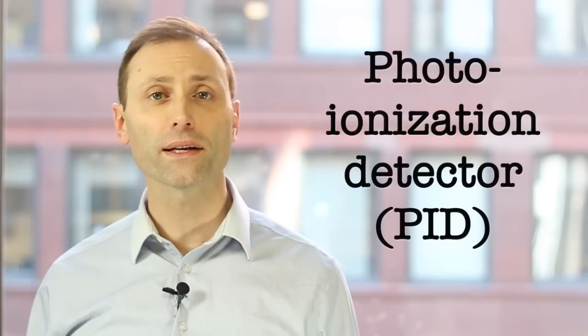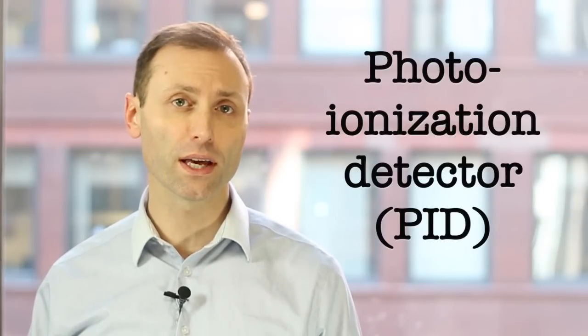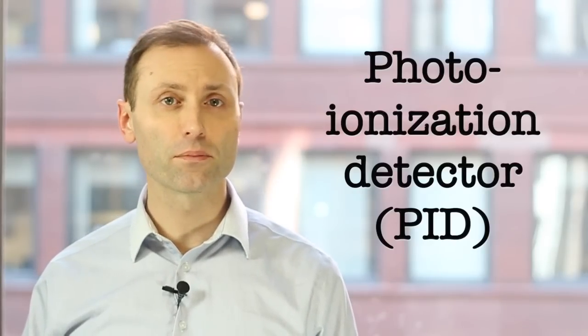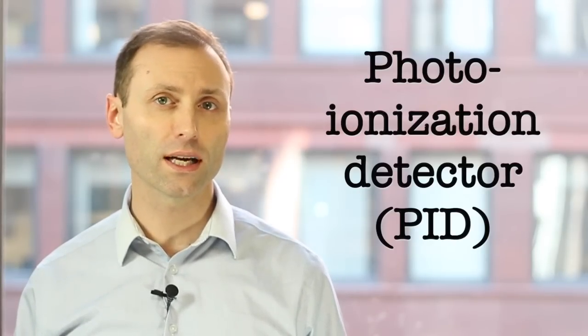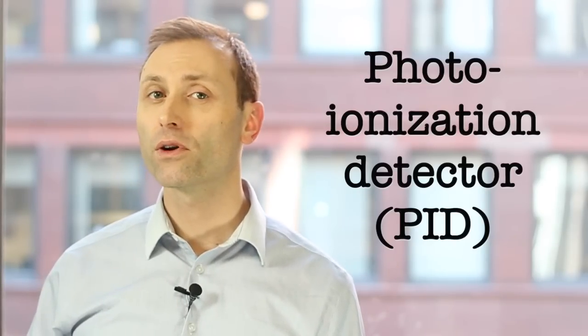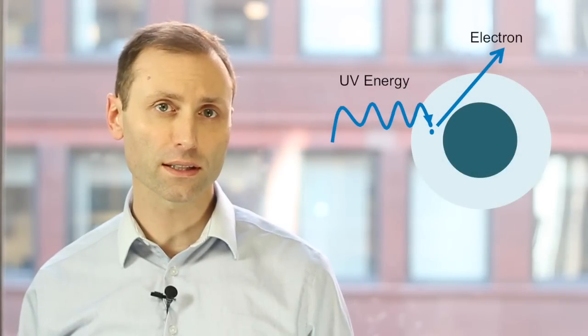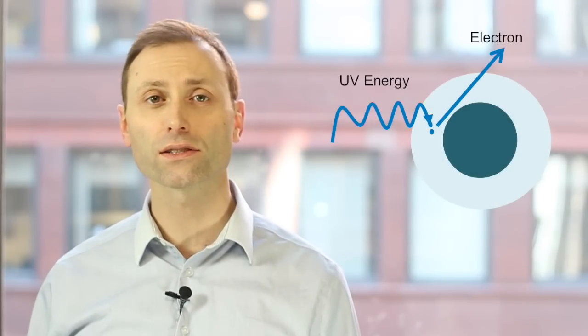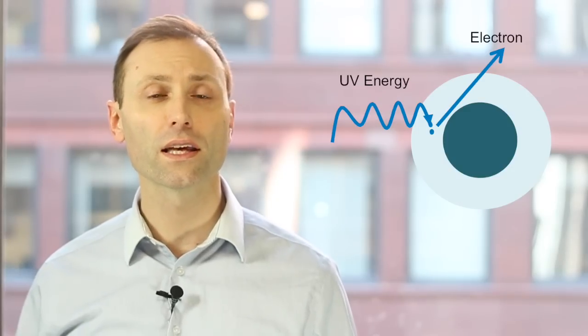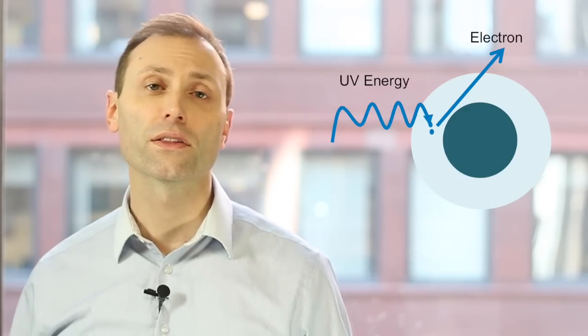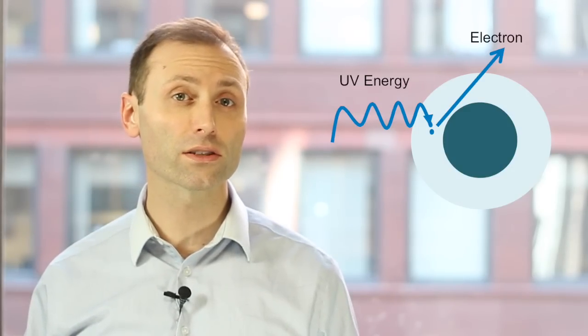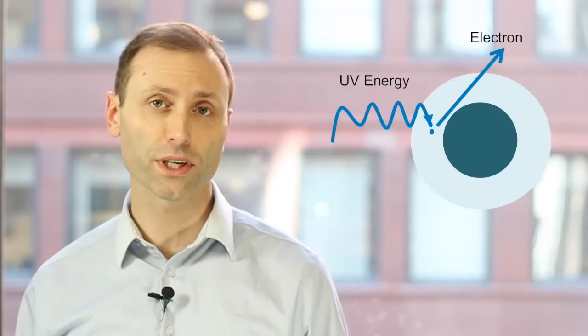A photoionization detector, which is also abbreviated PID, doesn't provide a breakdown of individual VOC concentrations. The term photoionization describes the process in which a high-energy ultraviolet light is used to remove electrons from VOC molecules, giving them a positive charge. The detector reads the ionic charge and converts it to a concentration.